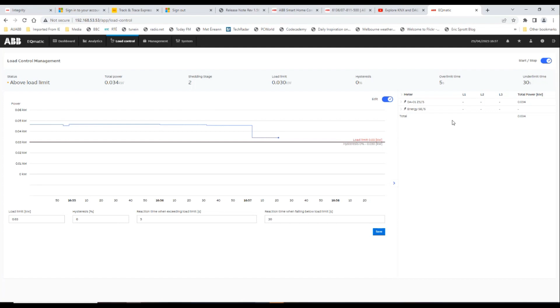And watch - the load shedding will time out in 30 seconds. We put a bit of hysteresis in there because you don't want it hovering around the limit and going on and off all the time, chattering relays and things like that. So it's good to be able to set those load limits in there and play with it.